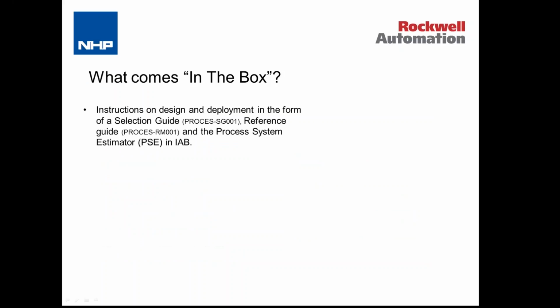So what comes in the box? Well, I've already mentioned some of this information, but instructions on how to put the system together in the form of a selection guide. So when we're designing our system up front, we would make use of this selection guide, and that enables us to correctly size the system, to correctly specify the right processor and the right network architecture to make the system. And then once we come to the implementation stage, we also have a reference guide, and that has more detailed information around the design of the system. So recommendations on how to structure the code in the controller, how to set up the various tasks, programs, routines to achieve the best possible performance.